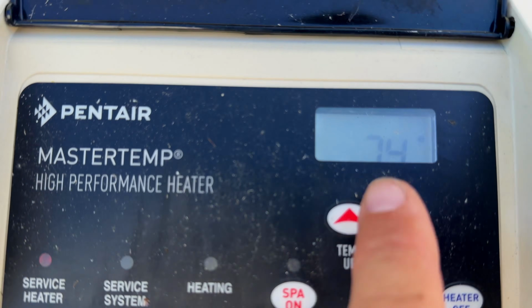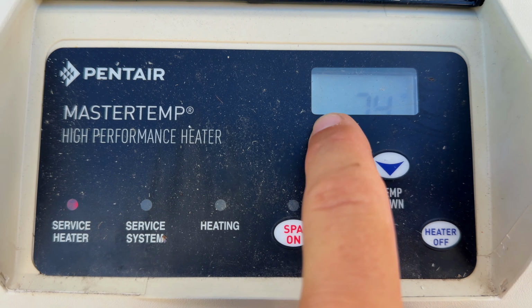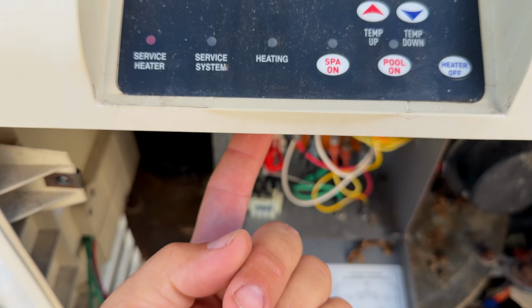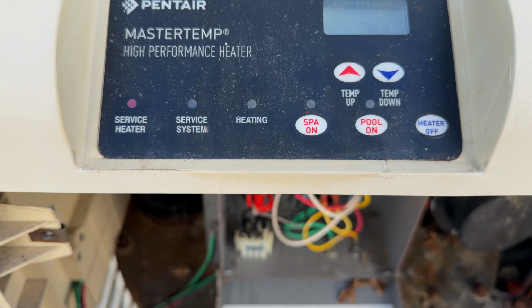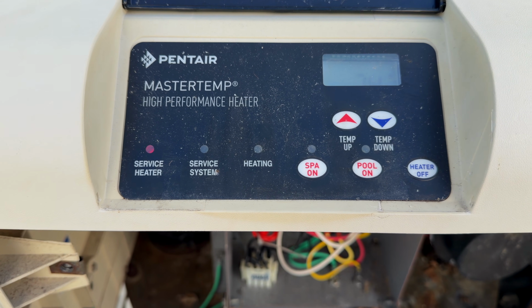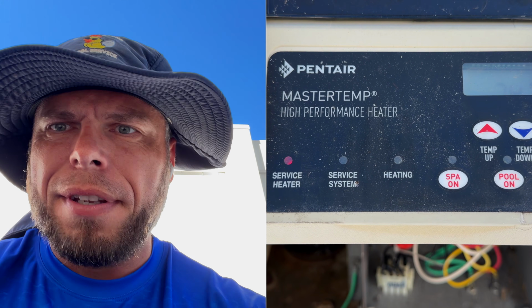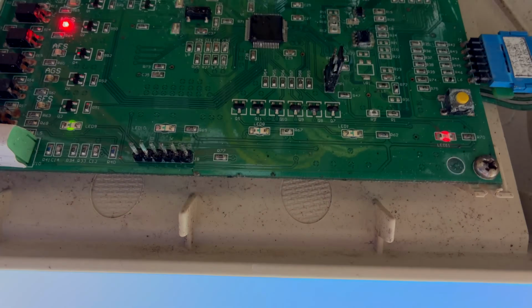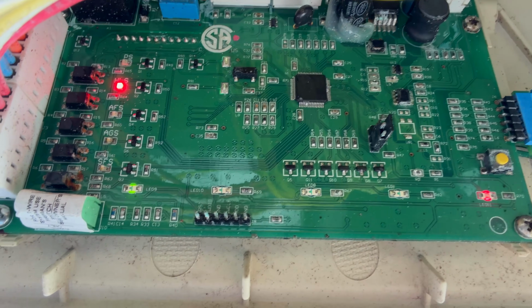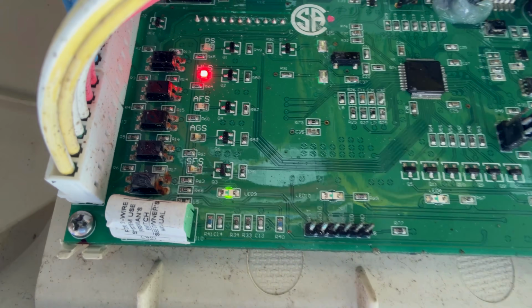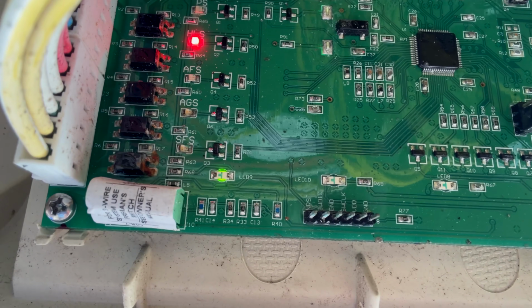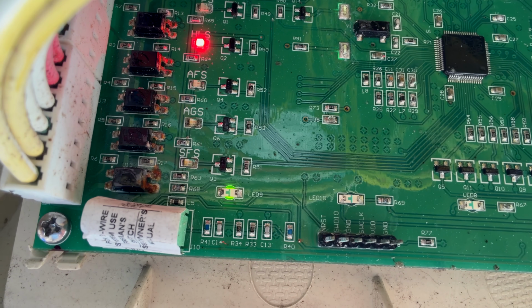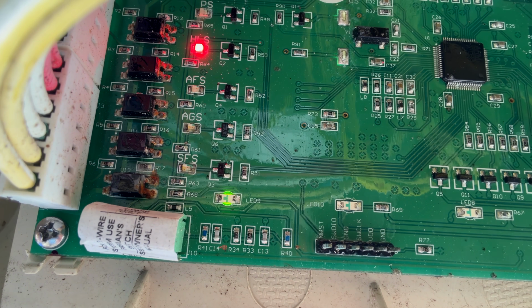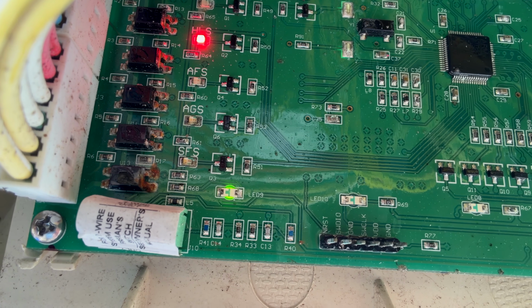And then from there, this panel doesn't give an error code outside here. It's actually underneath here. So what I'm going to do is flip the camera around and show you what to look for, and that will tell us where to look and move on from there. All right, guys, excuse this ugly face, but now we're going to take an underside view of the board here, and you can see that that light is lit, and it's going to be hard to zoom in, but right above it, it says HLS. And so the error code is the high limit switch.